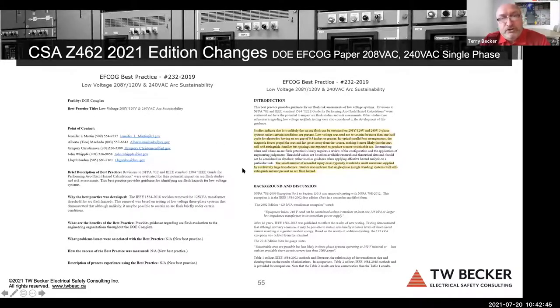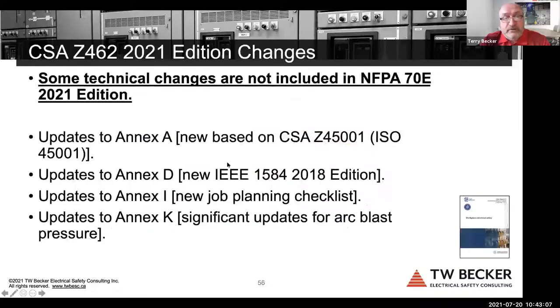So this is going to be hugely controversial. And it is in Z462. This is not in 70E. And as we move through this over the next year or two, I think this is going to be significant. And technically, it means that every household has a panelboard in it where an abnormal arcing fault could be sustained. So that's what also concerns me, right? But right now, I do not support that 240 volt single phase can sustain an abnormal arcing fault.